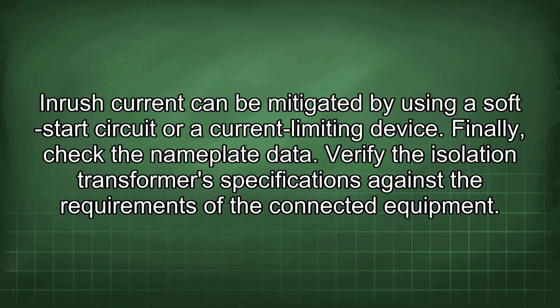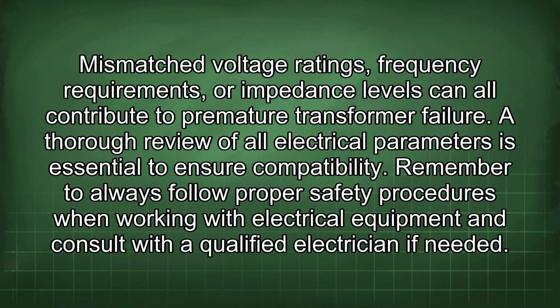Finally, check the nameplate data. Verify the isolation transformer specifications against the requirements of the connected equipment. Mismatched voltage ratings, frequency requirements, or impedance levels can all contribute to premature transformer failure. A thorough review of all electrical parameters is essential to ensure compatibility. Remember to always follow proper safety procedures when working with electrical equipment and consult with a qualified electrician if needed.